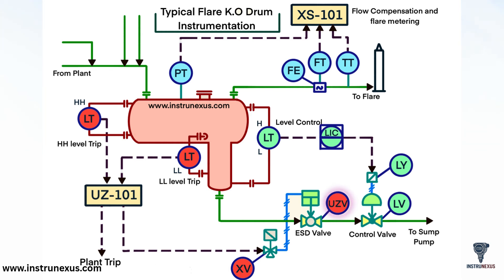Altogether, this system provides automatic level control, continuous pressure monitoring, and safety interlocks, ensuring that the flare operates safely and efficiently. By tracing each tag — LT, LIC, LV, UZV, and XS101 — you can easily understand how measurement, control, and shutdown functions integrate within the flare system.